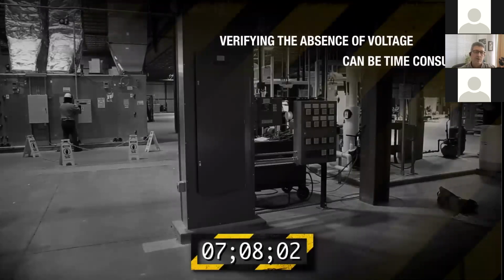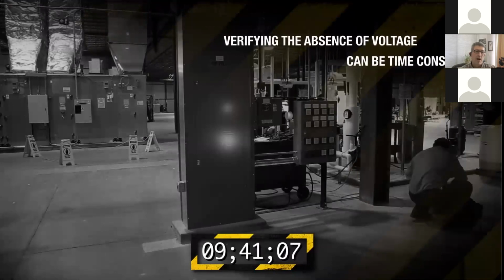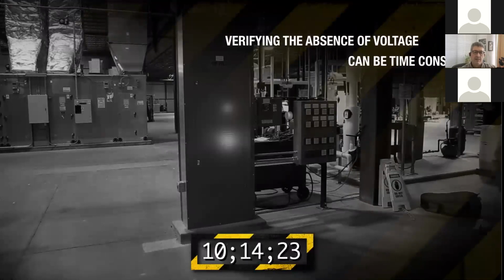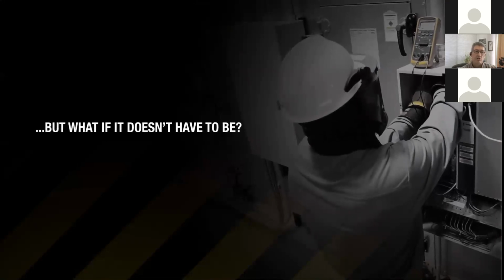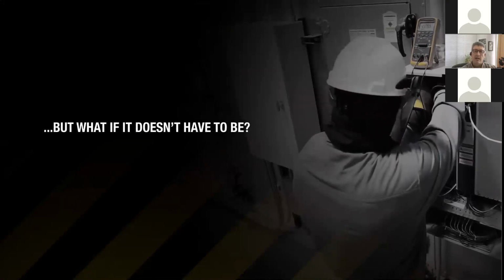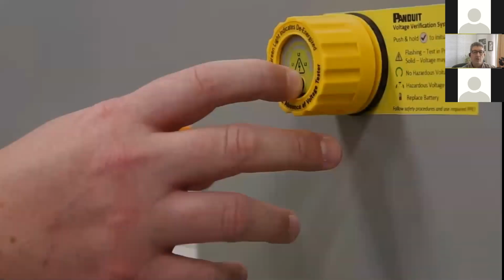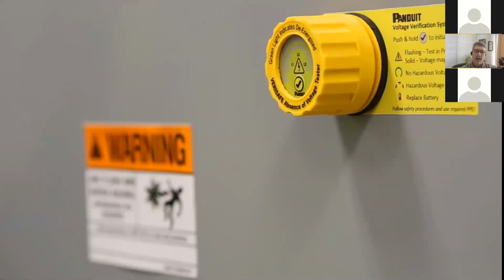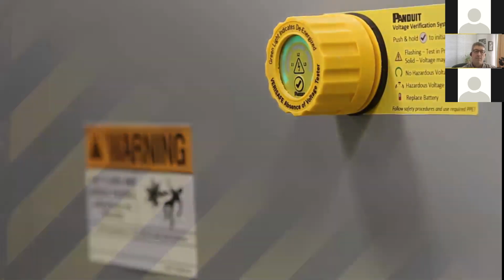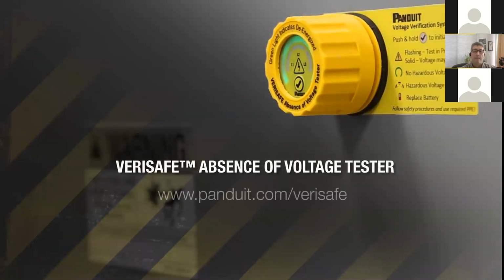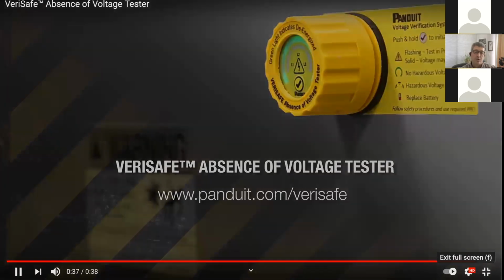So what you have here is an example of all the steps required to test for the absence of voltage. It can take some time, and it also means putting somebody in PPE in front of and exposed to energized parts, as opposed to pressing a simple button on the outside of a device to determine whether the system has been de-energized.